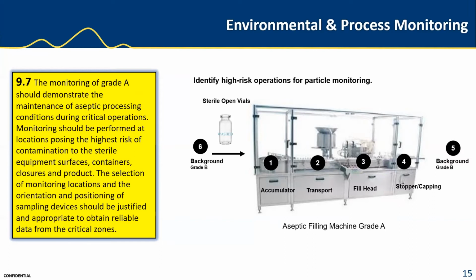Here we see an example of a grade A filling machine which has 4 locations to monitor in the grade A environment. We call these locations critical zones. We see location 1, the accumulator, has pre-washed open vials, so this would be deemed a critical location to monitor as the vials are open and at high risk. Location number 2 monitors the transport of the open vials to location number 3, the fill head, where the vials are filled with sterile product, before going to the stopper capping location at number 4.